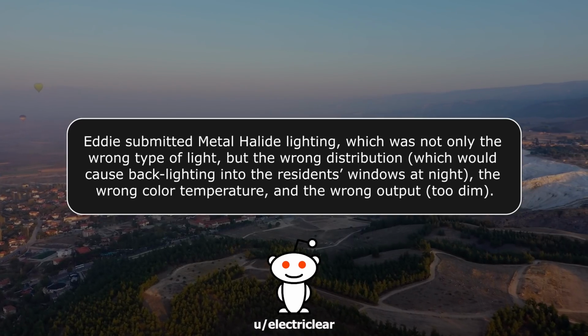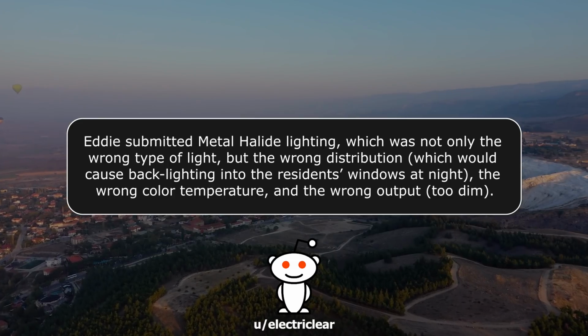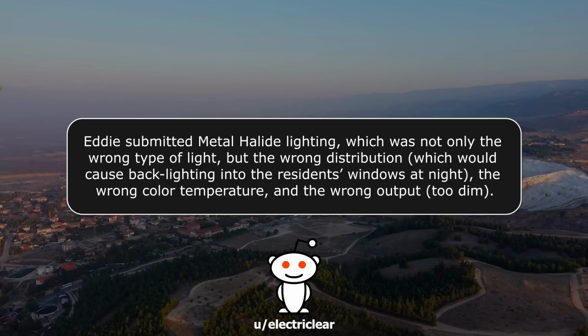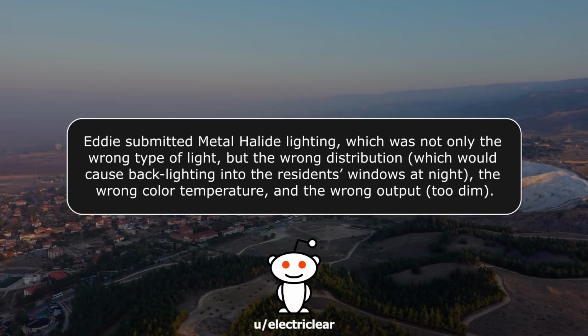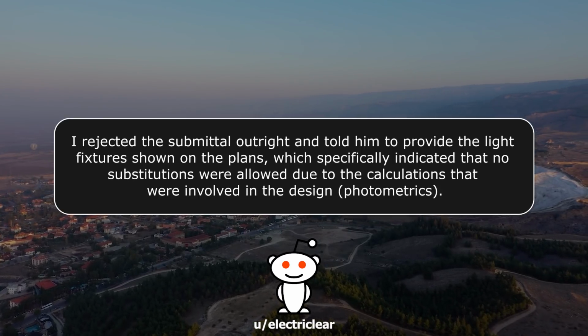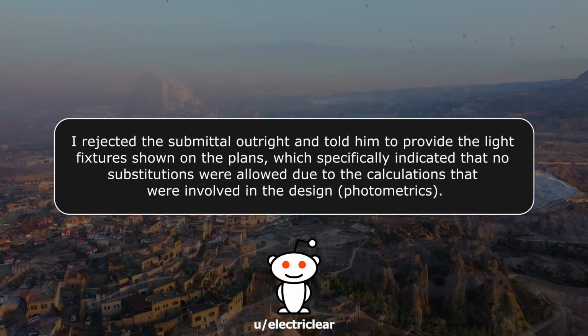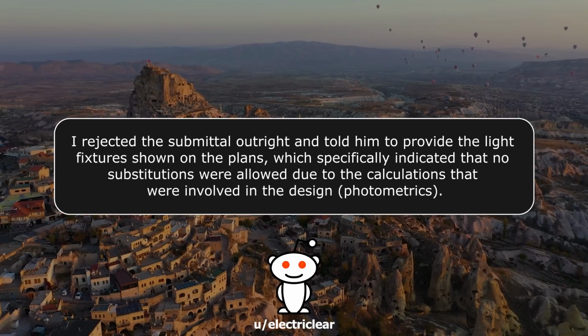Eddie submitted metal halide lighting, which was not only the wrong type of light, but the wrong distribution, which would cause backlighting into the residents' windows at night, the wrong color temperature, and the wrong output, too dim. I rejected the submittal outright and told him to provide the light fixtures shown on the plan, which specifically indicated that no substitutions were allowed due to the calculations involved in the design, photometrics.